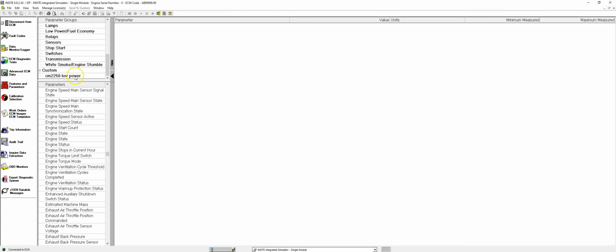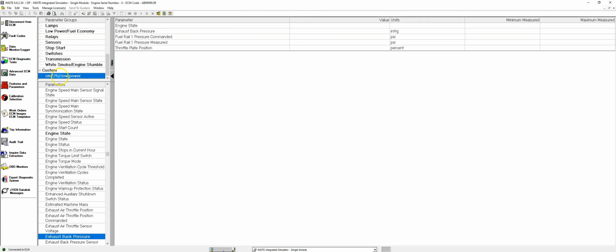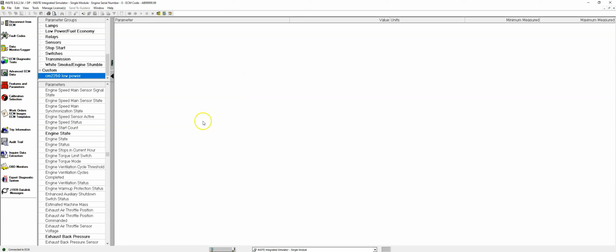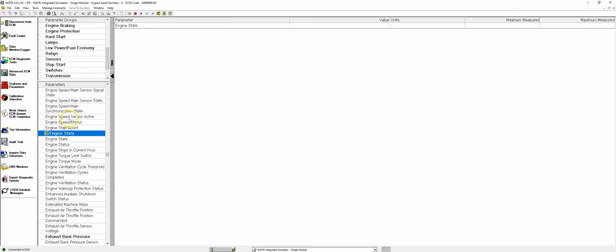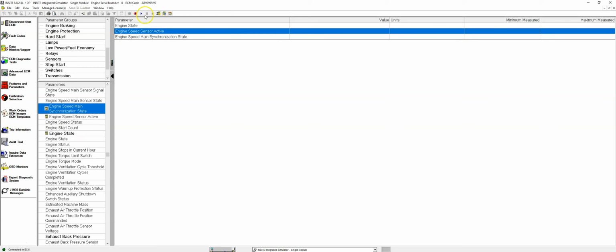Now we've got our custom group down here, labeled custom CM 2250 low power, which is what we made it. We click on that, and it brings up all the parameters we selected in our custom group. Like I said, if you want to remove these parameters, just right click, remove all parameters, and they're gone. Then you can select another group, or go back and choose each parameter individually that you want to monitor. You hit play, and it starts monitoring that data.